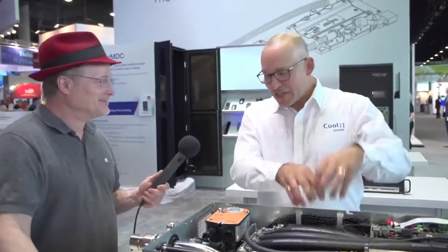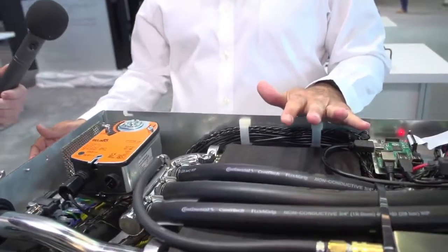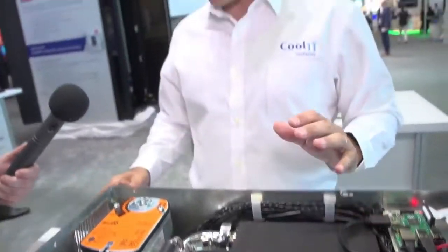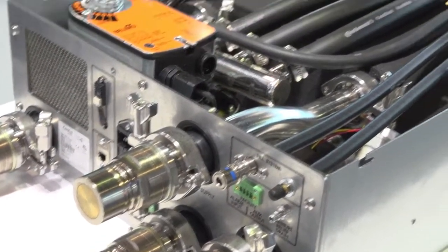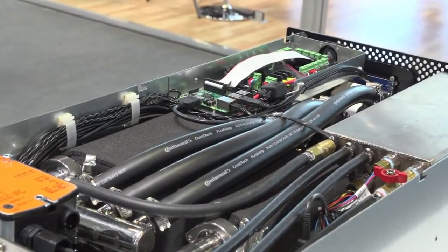So it's got a large heat exchanger in here. It has a liquid-to-liquid heat exchange profile, so you need a facility water feed, either warm water or chilled water, and it will transfer all the heat gathered from the servers into the facility water flow, so it can potentially be reused in some cases. We have sites doing energy reuse for heating buildings or melting snow on the sidewalk, or even some trying to do energy generation, which is pretty cool.